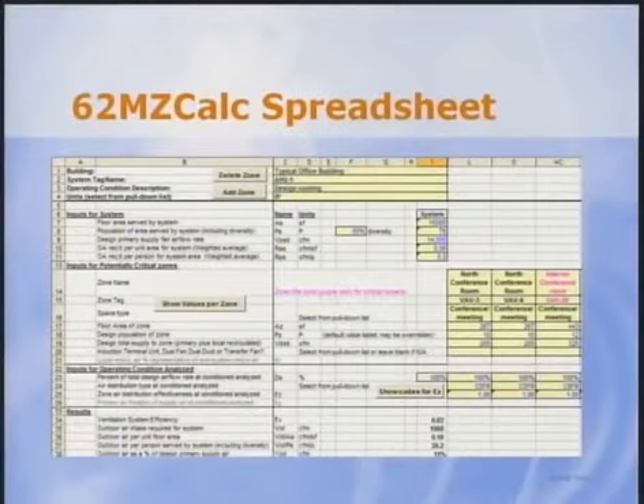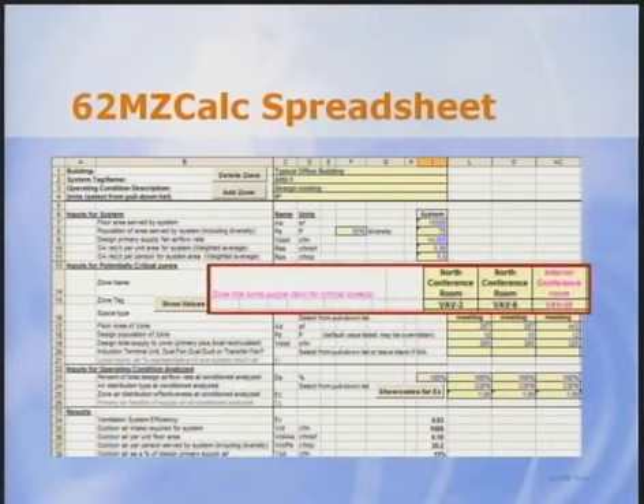This screenshot shows the design cooling condition. The critical zone in this case, highlighted by the spreadsheet in purple, is an interior conference room. This zone can be made to be non-critical by installing a series fan-powered mixing box with the supply air rate a bit above the design primary cooling rate. The next most critical zone in this case, the 2 north conference rooms, would then determine the design outdoor air rate. Now let's look at the heating conditions.